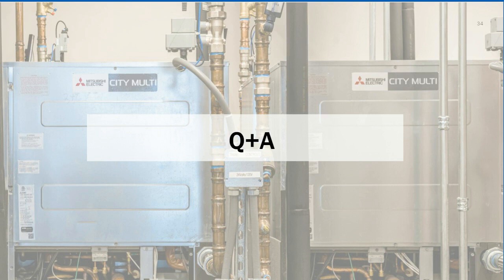Yeah, the maintenance side of it is making sure you're maintaining proper water quality for this closed loop condenser water system that runs through the building and through this unit. And that's really a pretty standard condenser water maintenance program. Those condensing units don't really have a whole lot of moving parts that you change out. Definitely on the fan coil unit side, as with every air conditioning unit, you want to make sure you're changing out filters often, like you're supposed to. But really just keeping up with the water treatment and keeping up with filter changes is the main thing to do with this type of system.